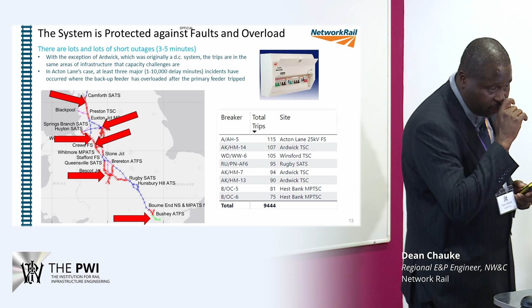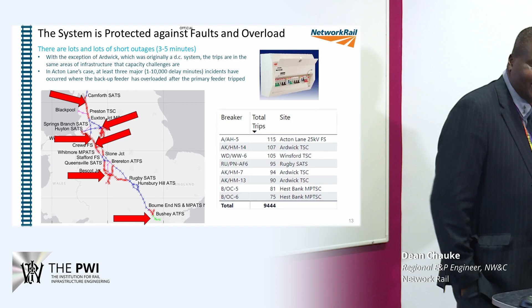Arguably, for K11 circuit breakers, which are oil-filled, I have to filter the oil or change it every 30 operations. What's happening with freight nowadays is once a double-headed class 90 runs through, you get a single-ended trip. Because the circuit breaker doesn't know whether it was a load tripping or otherwise, my maintenance standard says, for the thing not to blow up, go and change oil or filter. Yet in normal practice, if nothing has tripped, I only have to change every 2 years. So it's becoming a maintenance burden.